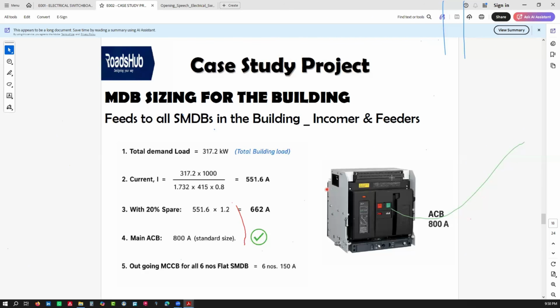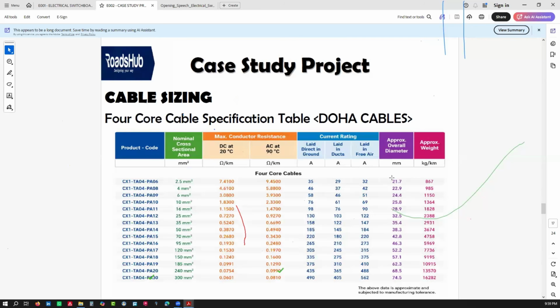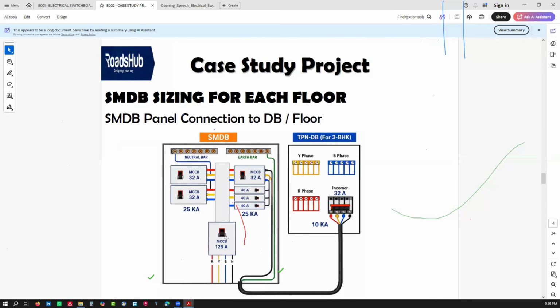And now remember, in the DBs we are using MCBs. MCBs actually have what we call a lower kA value. They trip very fast. So when you're working with high power, you now need systems that can handle a lot of kA. And from our selection here, I forgot to tell you, here we are using MCCBs, but in the DBs, we are using MCBs. So MCCBs have the highest kA value because they are handling a lot of power. DBs have up to 10 kA, and you can read it on your breakers. It is written there. This is the amount of fault current they can handle.